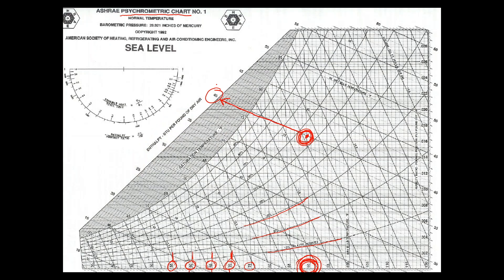And if we take that air, and in an air conditioning scenario, often what we would do is cool the air with a cooling coil, we hit the saturation curve, and we cannot continue to go through this direction. You just can't do it. So, what happens when it starts to rain, we cool it down to the dew point, it starts to rain. We actually follow the saturation curve like this. And it would not be uncommon to cool, say, all the way to somewhere around, say, 50 degrees.